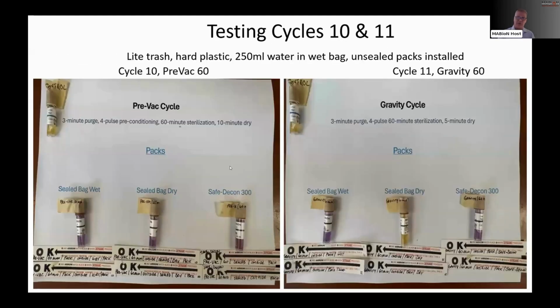So one more. Now you're saying, okay, let's run it a little bit longer and see what happens. So what I ended up doing here is I switched on the last two, and on this one I went to 250 milliliters of water, which was what was recommended. Then I ran the pre-vac cycle. The wet bag here, as you can see, we got good penetration. These bags did break. Safe-Decon worked like it's supposed to, and you can see that we got the good steam, and then we got the good BIs.